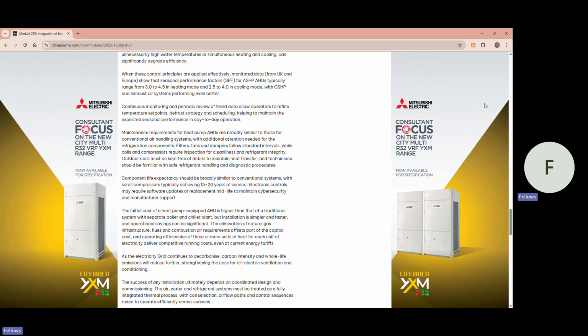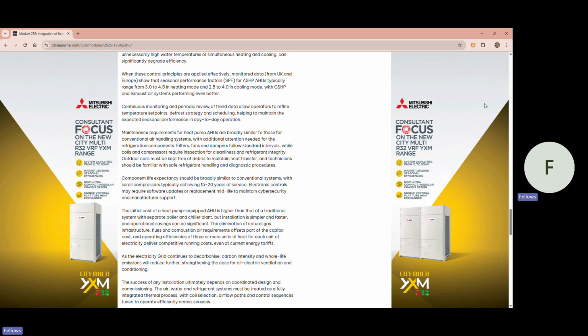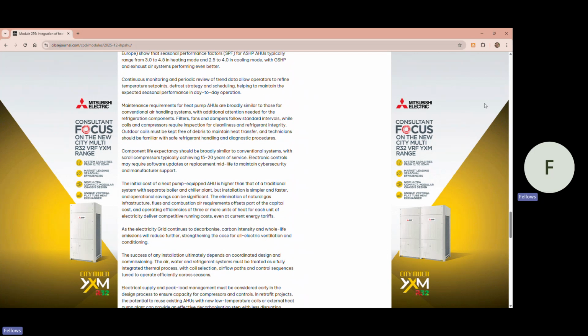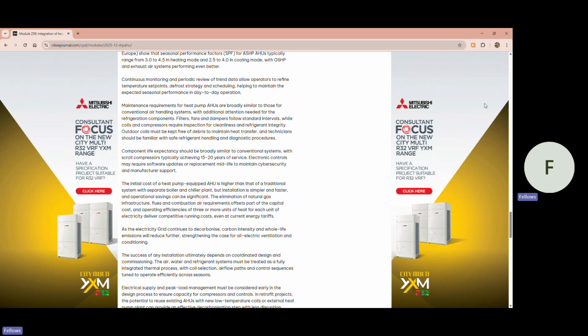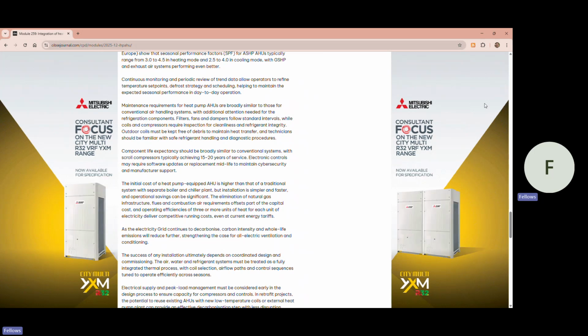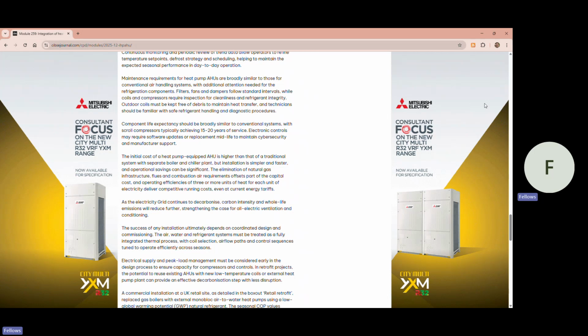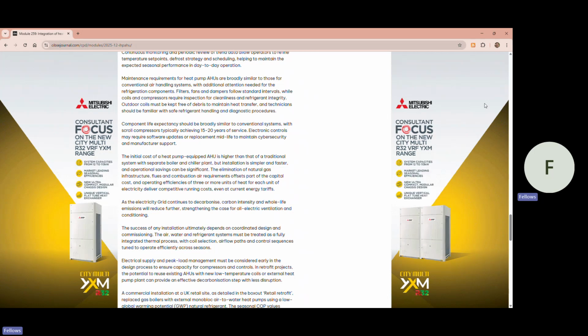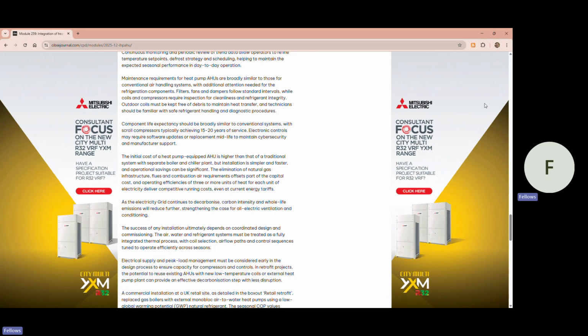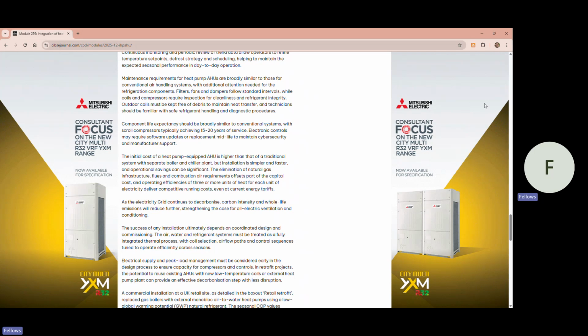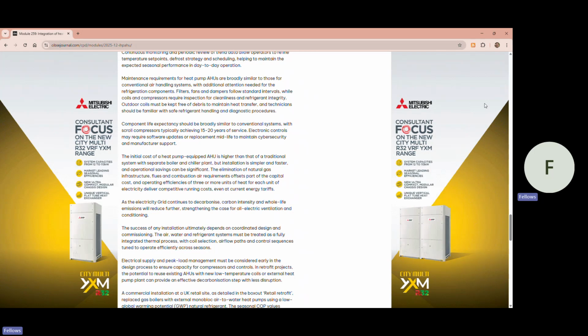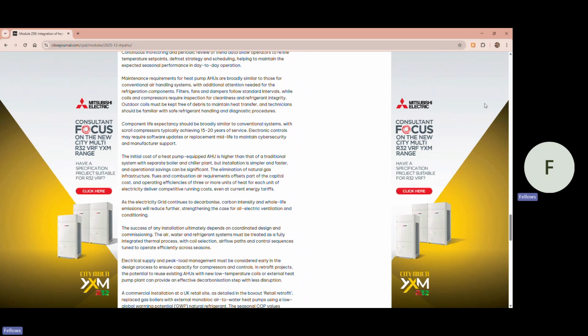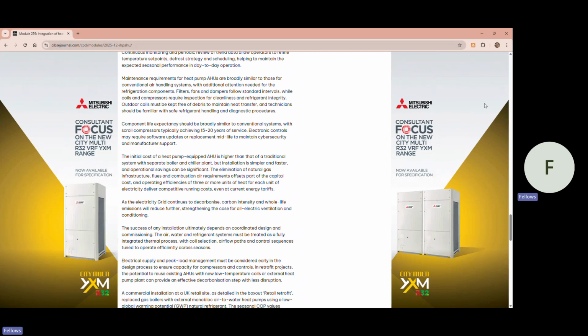Component life expectancy should be broadly similar to conventional systems, with scroll compressors typically achieving 15 to 20 years of service. Electronic controls may require software updates or replacement mid-life to maintain cybersecurity and manufacturer support. The initial cost of a heat pump equipped AHU is higher than that of a traditional system with separate boiler and chiller plant, but installation is simpler and faster, and operational savings can be significant. The elimination of natural gas infrastructure, flues, and combustion air requirements offsets part of the capital cost, and operating efficiencies of 3 or more units of heat for each unit of electricity deliver competitive running costs, even at current high energy tariffs.